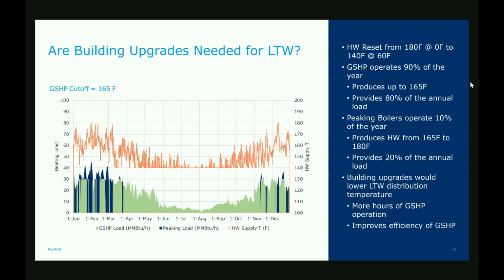The next thing we look at is within the buildings: do they have to upgrade their HVAC systems? Do they have to go to 140-degree hot water within the buildings? We all know heat pumps work best the lower the temperature. The technology is continuously updating, getting warmer and warmer temperatures. 180 is not out of the question, but your COP gets impacted.